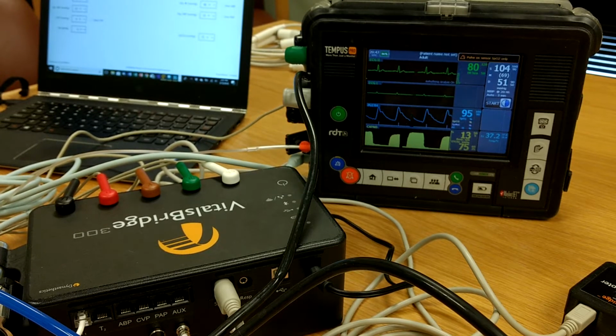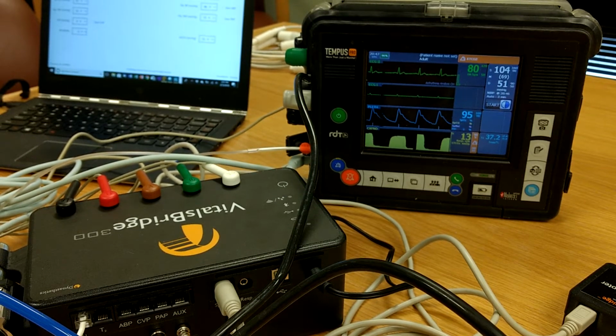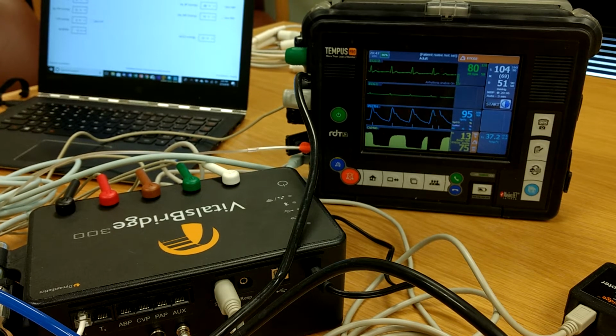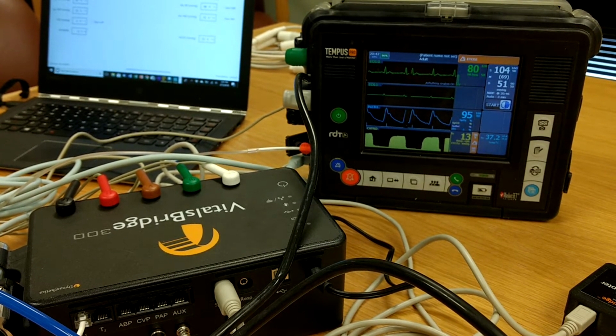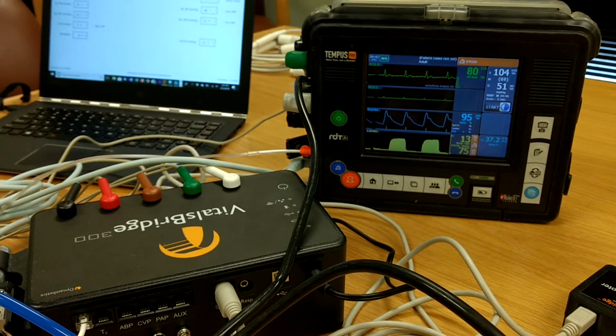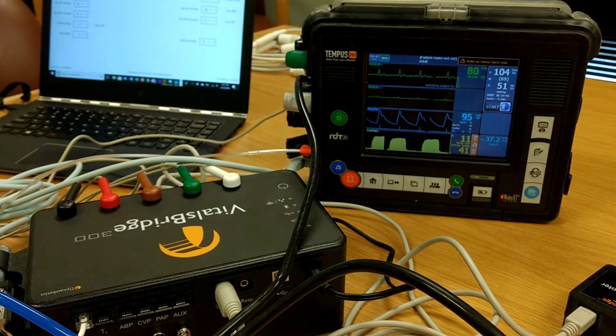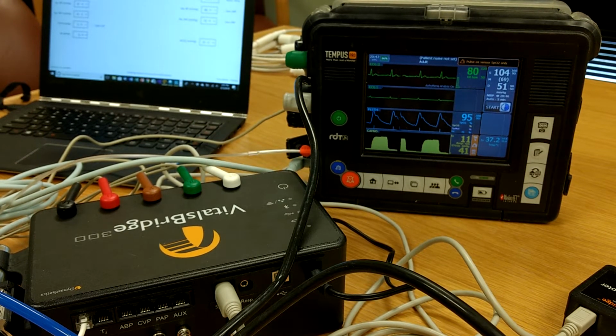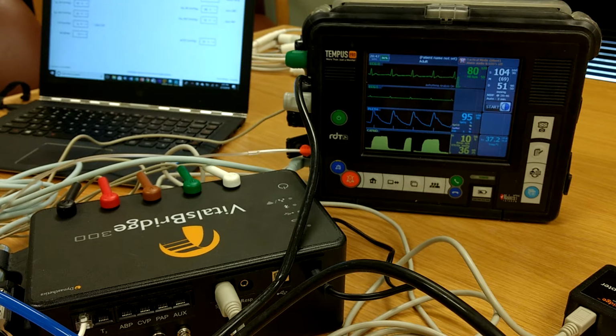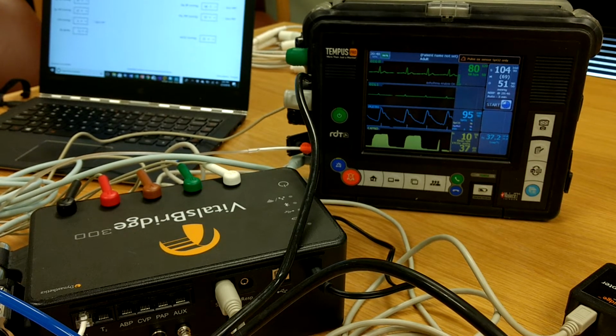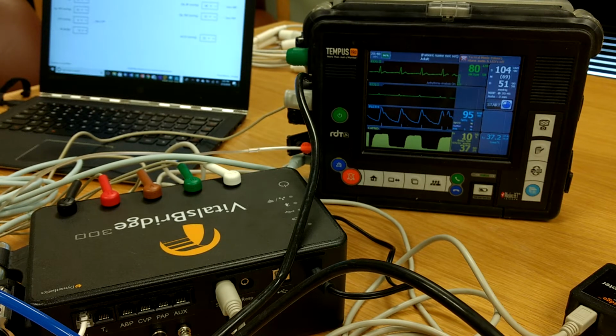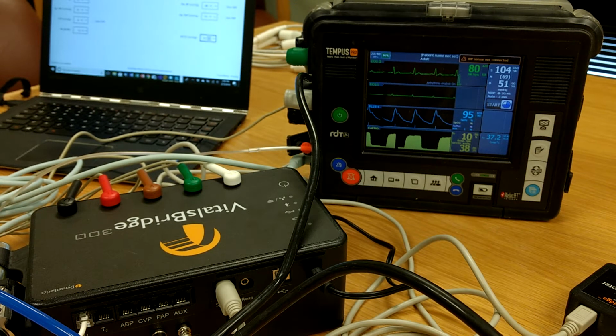Let's see, right now we have our respiratory rate set for 12, our end-tidal CO2 set for 34. The capnometer is showing the highest number that it's seen recently. They tend to do that. They lock on the high number, but then after a while they settle down. So let's just see, now we've got it set. It's showing 37, 38, we've got 35. There is an option to calibrate the capnometer.